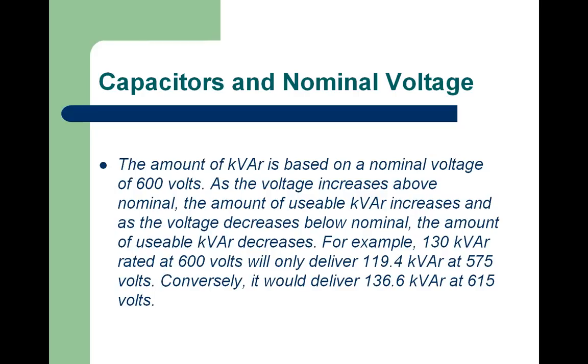Typically, kVARs are rated in Ontario here at 600 volts. So at 600 volts, 130 kVAR would deliver 136 kVAR at 615 volts and 119 kVAR at 575. Typically, when you're at your peak load in your facility, that's when you need the most kVAR for correction, and that's also when your voltage is likely going to be at its lowest. So every site needs to be looked at individually to determine how many kVAR you need, to go over a little more or less.